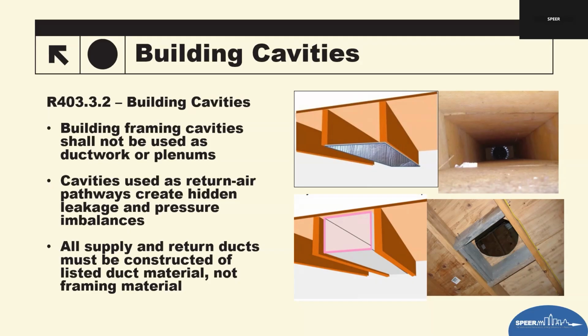These hidden leaks skew the blower door and duct test results because the system is essentially pulling from an unconditioned space. That goes deeper than what I want to go into here, but if you have a failing blower door test, sometimes it's accompanied by severe duct leakage. That's why, again, we don't want building cavities being used as supply and return. So the takeaway is that all supply and return ducts must be constructed from a listed duct material, not framing cavities.